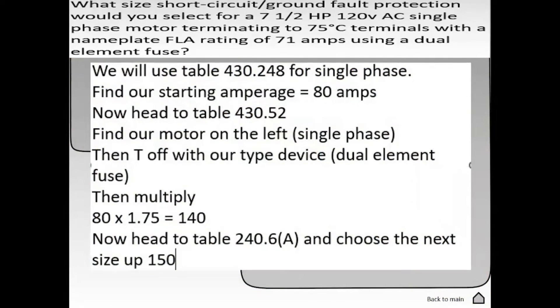We take our original FLC multiplied by 1.75 and that gives us a new amperage of 140 amps. Now we're going to head over to table 240.6A and choose the next standard size up. We're allowed to choose the next size up when we're doing short circuit ground fault protection. And the correct answer is 150.